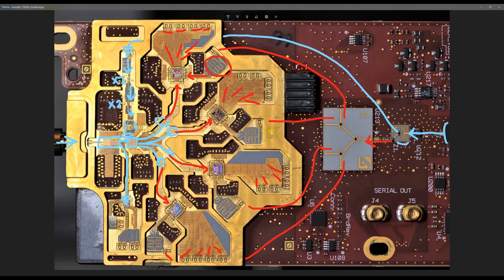So now your 110 gigahertz front end signal has now been broken into 16 differential pairs, and these 16 differential lines can now be fed into the A to D converters because now they're low enough in bandwidth. Each of them has a bandwidth of just under 8 gigahertz. Now 16 times 8 is 128 gigahertz. The bandwidth of the scope is limited to about 113. So each of these process a little bit less than 8 gigahertz of signal. But now that you have this, you can feed that directly into an A to D converter.